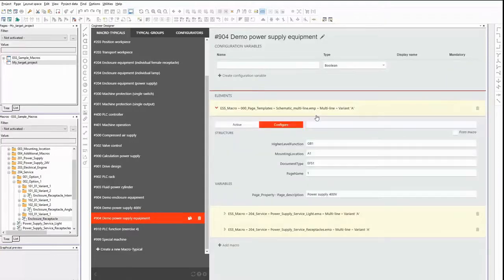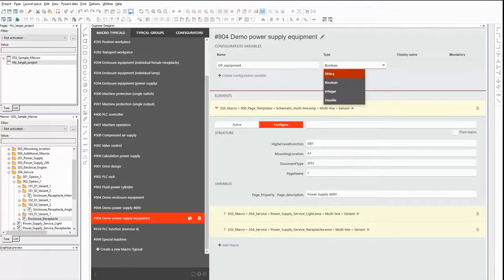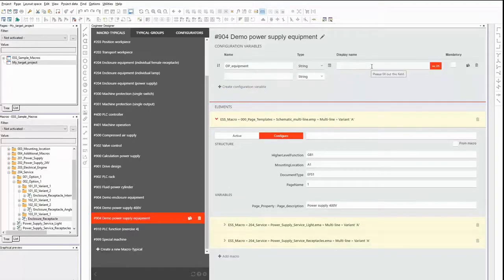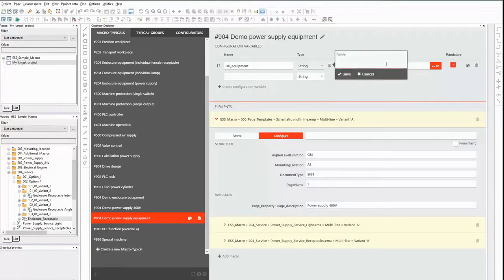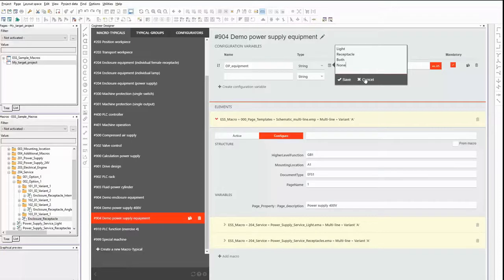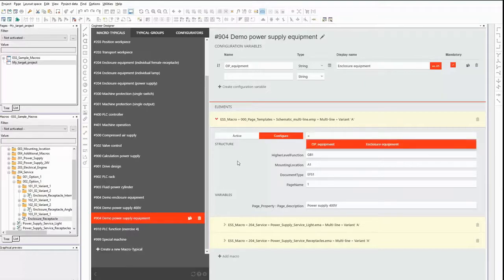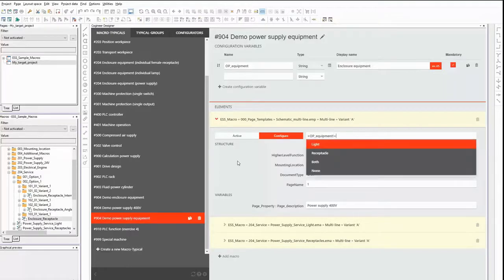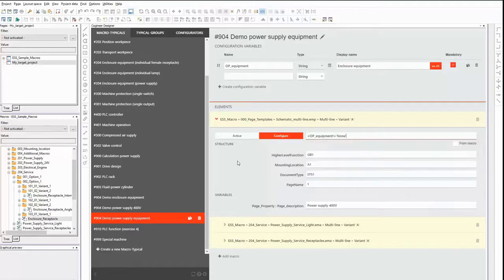This macro typical contains the obligatory page template and the single wires that are used as power supply for the enclosure equipment. Depending on the selected option in the configurator, only one, both, or none of them are needed when generating the schematic. I need a configuration variable to set this up, but this time there are more options. That's why I choose a variable of type string. It should be possible to choose between light, receptacle, both, or none of them. For every option I add one predefined value for the configuration variable. Now I can use these predefined values to set up conditions in my formulas for the macros. The page template should be used for all values except the value none, and that's the expression I enter in the formula.